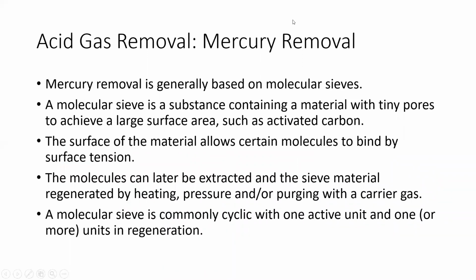We'll talk a little bit about mercury removal. Mercury removal is generally based on molecular sieves, and a molecular sieve is a substance containing material with tiny pores to achieve a large surface area, such as activated carbon. The surface of the material allows certain molecules to bind by the surface tension, and the molecules can later be extracted and the sieve material regenerated by heating, pressure, and or purging with a carrier gas. And a molecular sieve is commonly cyclic with one active unit and one or more units in regeneration.